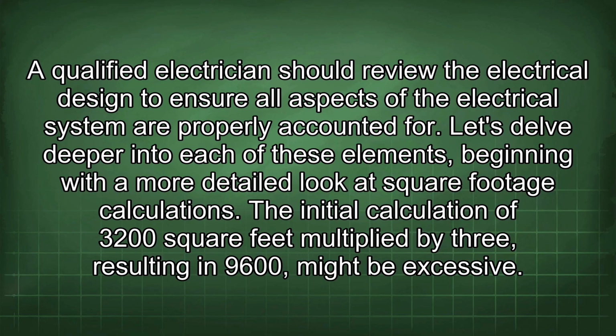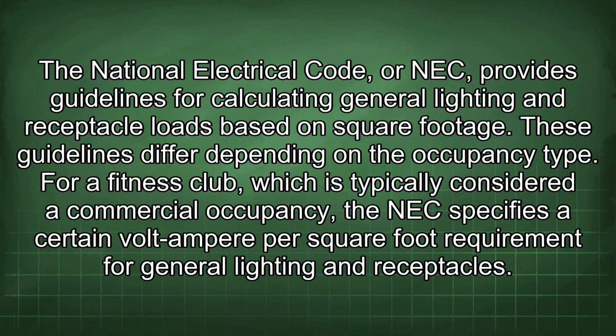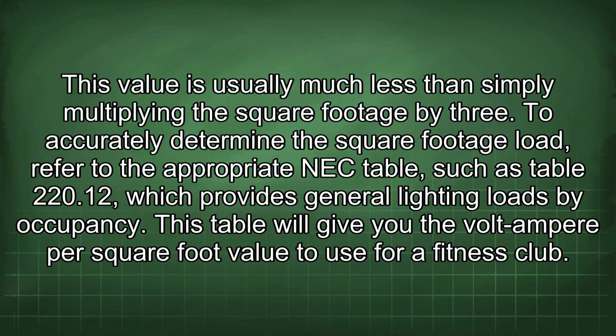Let's delve deeper into each of these elements, beginning with a more detailed look at square footage calculations. The initial calculation of 3,200 square feet multiplied by 3, resulting in 9,600, might be excessive. The National Electrical Code, or NEC, provides guidelines for calculating general lighting and receptacle loads based on square footage. These guidelines differ depending on the occupancy type. For a fitness club, which is typically considered a commercial occupancy, the NEC specifies a certain volt-ampere per square foot requirement for general lighting and receptacles. This value is usually much less than simply multiplying the square footage by 3.